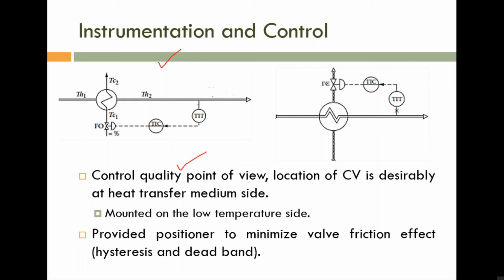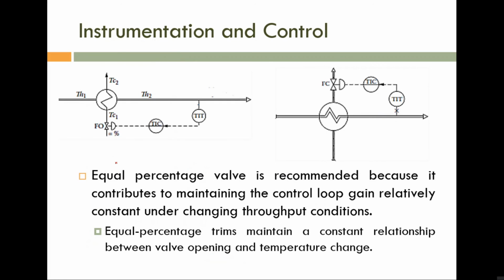What is the purpose? In order to reduce the effect of valve friction. What are the effects? Hysteresis and dead band, especially dead band. That is a big effect of valve friction. Now we are using an equal percentage valve, and you know why we are using an equal percentage valve. What is the importance of an equal percentage valve?